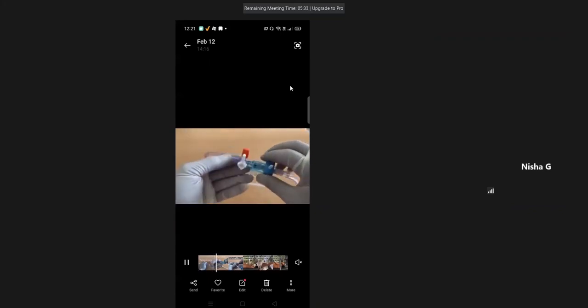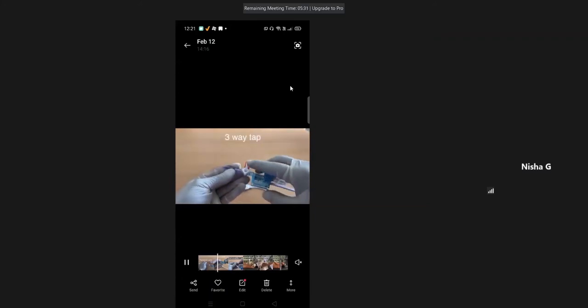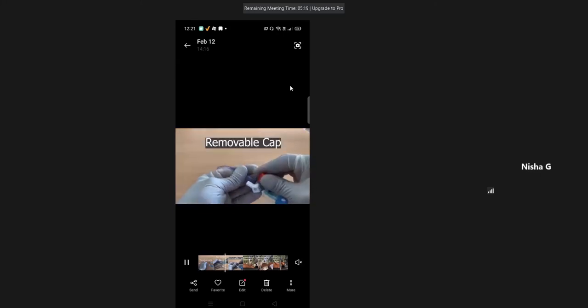In front of that, can you see that there is a white color 3-way? So now he's showing you that the point where he's touching is off. Wherever he turns it, that is closed, so closed to the atmosphere. Patient end is closed over here. And this is the opening of the three-way, so I can attach a syringe over there. I can aspirate my blood sample. I can flush NS through it and clear the arterial line. So that's from where I can do my blood sampling.